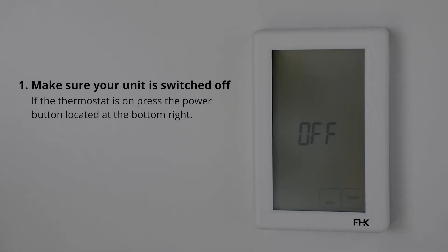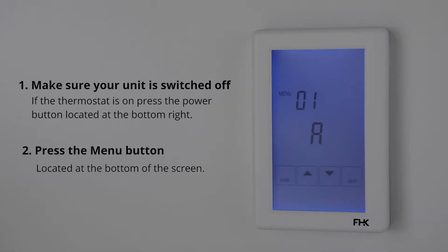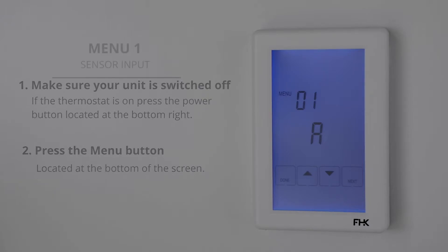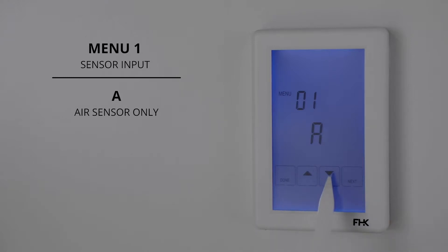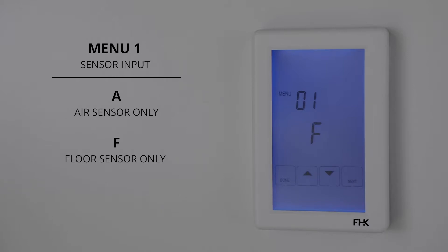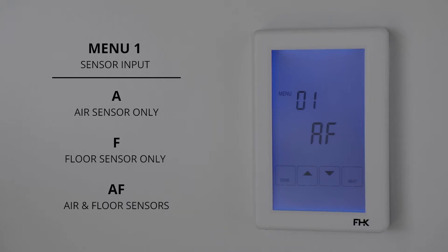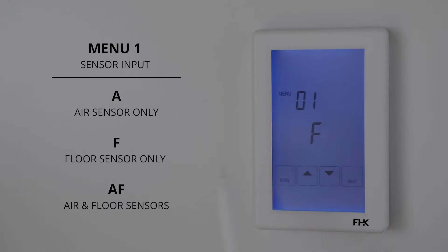Once it is off, press the menu button. You will see menu 1 at the top of the screen. Menu 1 allows you to choose which sensor the unit will use to determine the floor temperature. You can use the up or down arrows to select between three options: A, where the unit will use the built-in sensor; F, where the unit will use the floor sensor only; or AF, where the unit will use the air and floor sensor together. In this video we will select F mode for floor sensor only.